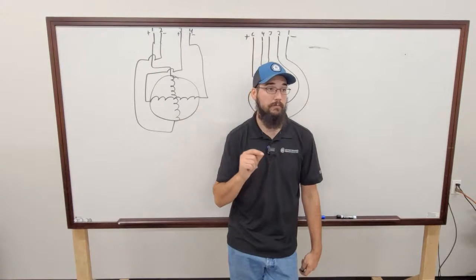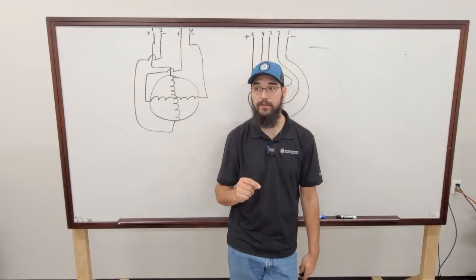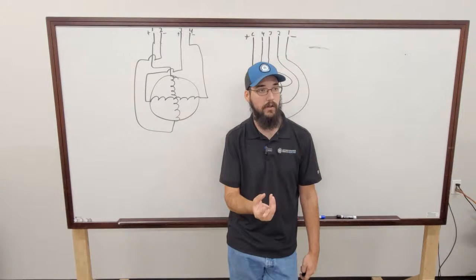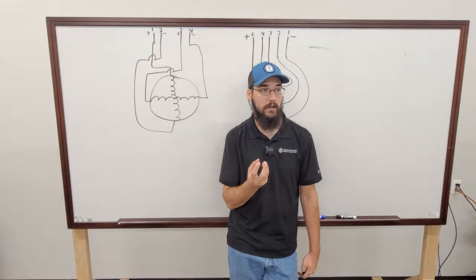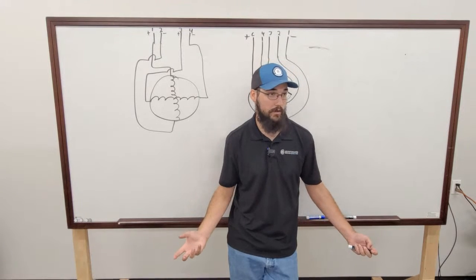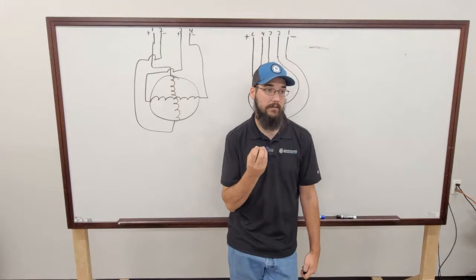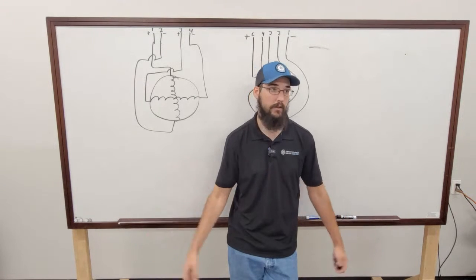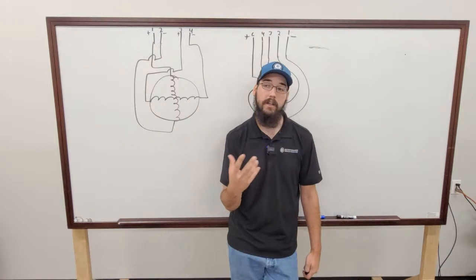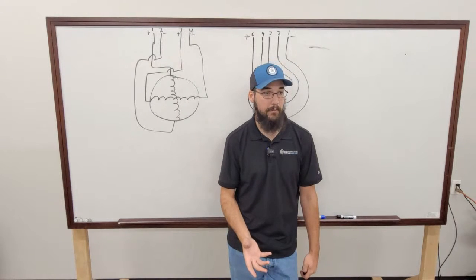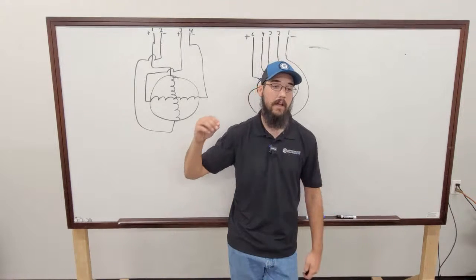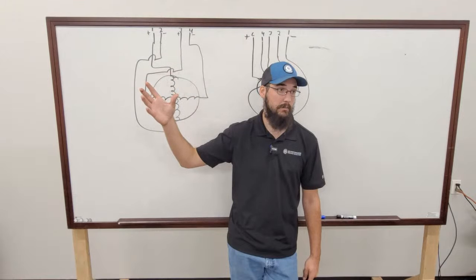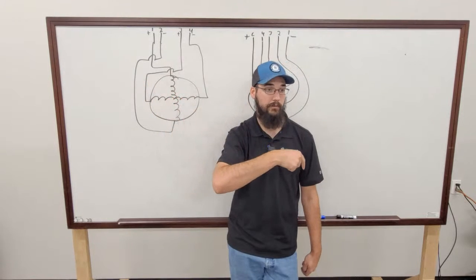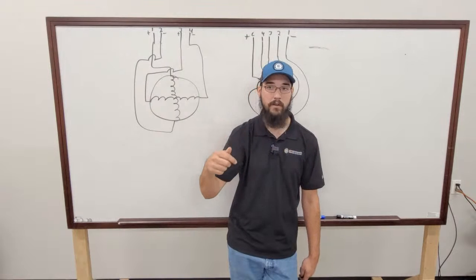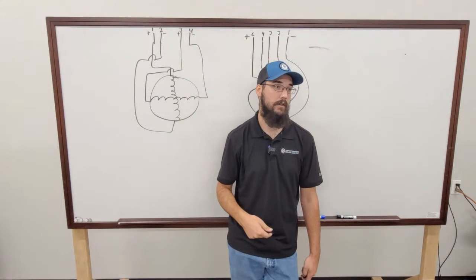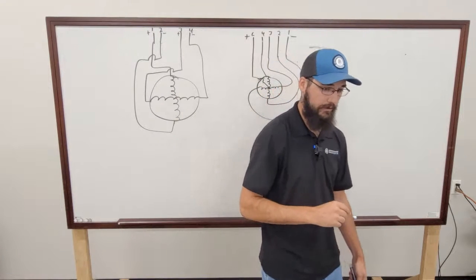The other thing to note: do not put power on those sensors without water on them, because that will allow them to overheat. They're meant to be inside of the water stream, and that can damage the sensor to where it just ain't gonna work. So be mindful of that. If you're walking into a system where you've got to drain the evaporator or the barrels for any reason, and you still have power on the machine, meaning those sensors are still reading something, unwire those before you drain that water out. That will protect your sensors.